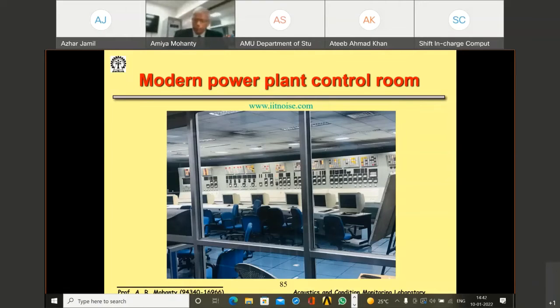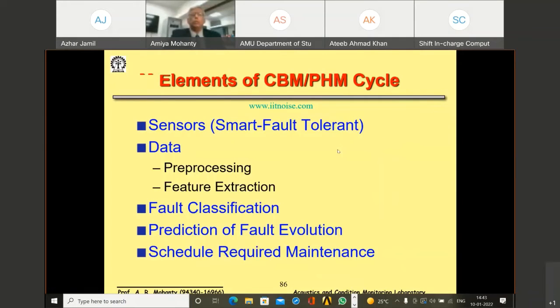So again, I have told you about sensors - accelerometers, velocity probes, eddy current probes, Hall effect sensors, current transformers, etc. What if this sensor has a problem? Today the technology is such that this sensor will tell you if there is an open circuit; the sensor will warn you. Sensors known as TEDS-based sensors have an electronic chip embedded in them where its sensitivity and its identity are stored. So as soon as you connect to an analyzer, you do not have to set up the sensitivity of that sensor - it is automatically read by the analyzer, and you will be measuring in the mechanical unit the sensor was designed to measure. So smart, fault-tolerant sensors are very, very important.